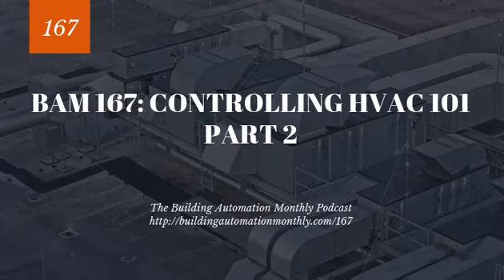So safeties, the primary safeties I tend to look at are pressure safeties, contact safeties, temperature safeties, and life safeties. So pressure safeties, you have low static and high static. Especially with variable air volume systems that have VFDs, you vary the speed or the frequency. VFD is frequency, VSD is speed, but they roughly have the same effect. You vary essentially the volume of air that is being pushed through the ductwork.